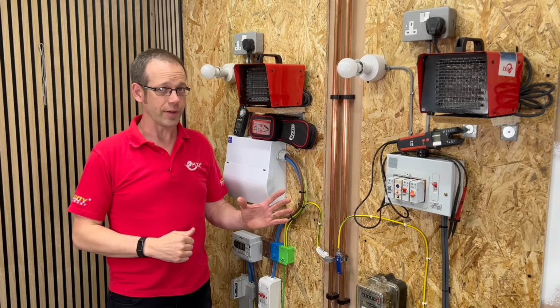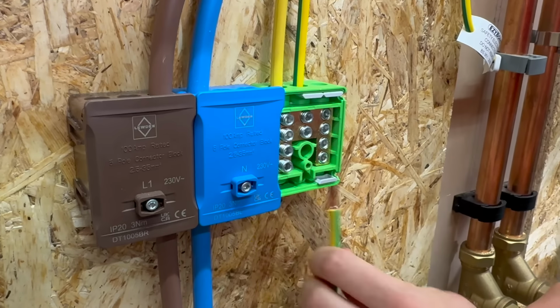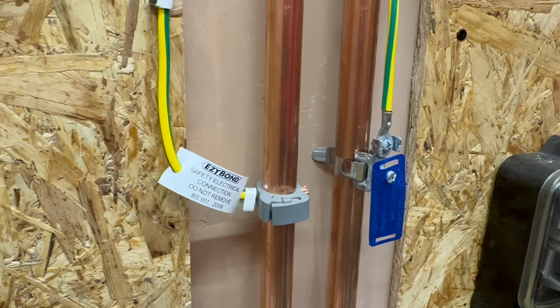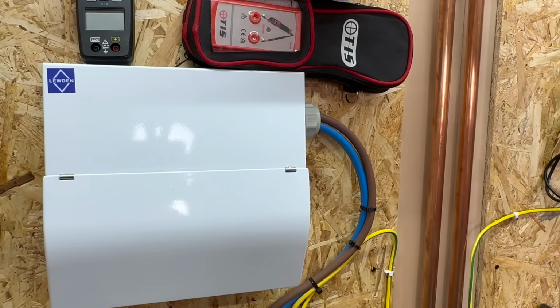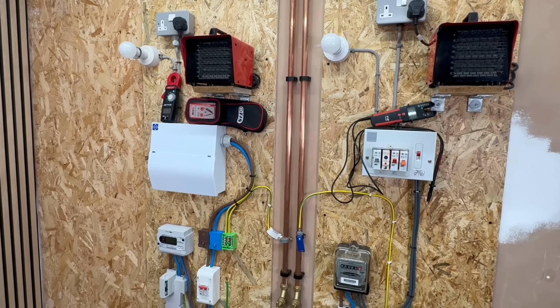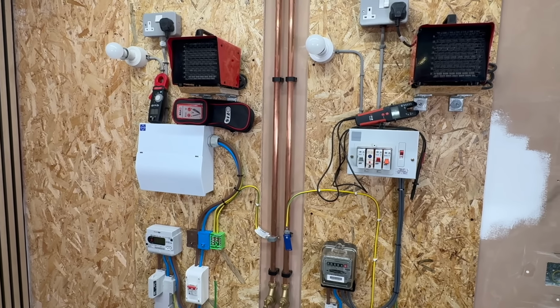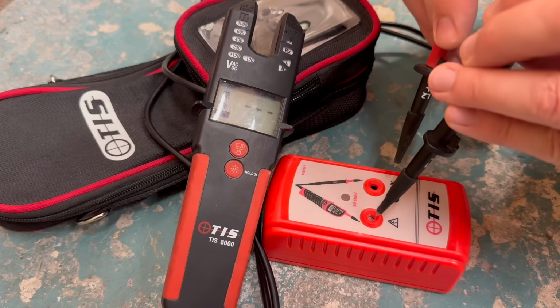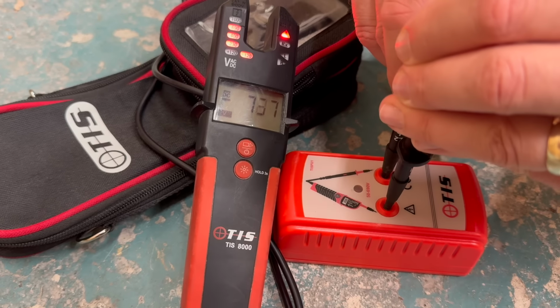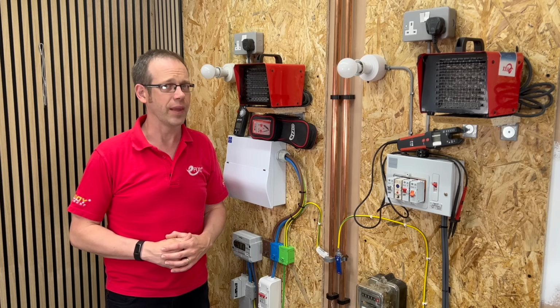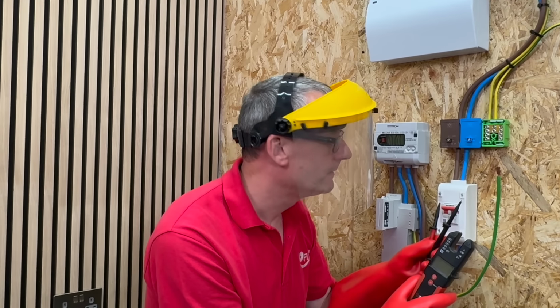This is terrifying. I've disconnected the main earthing conductor, and not only is the main earthing terminal live, this water pipe is also live, and so are all the exposed conductive parts of this installation, as are all the exposed and extraneous conductive parts in the house next door. And worst of all, I carried out the safe isolation procedure, and I'm still potentially dead. So what's gone wrong? And was there anything I could have done to protect myself from this?